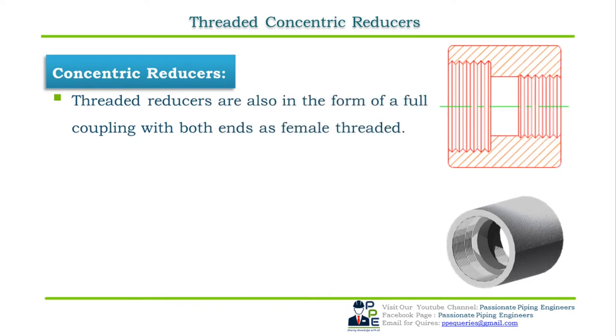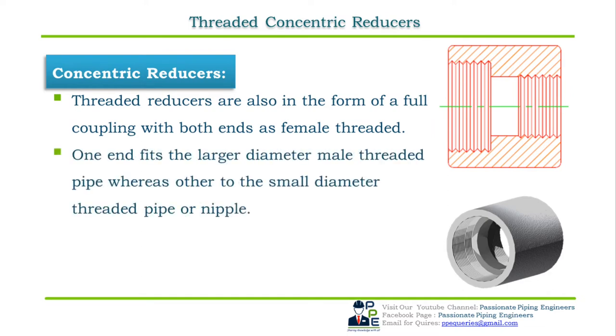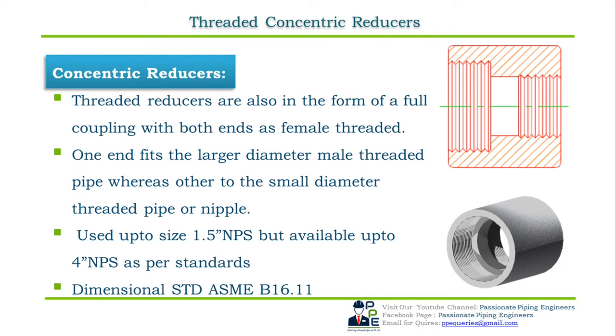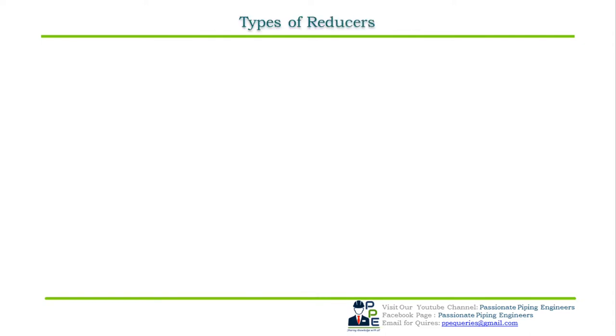Threaded concentric reducers are also in the form of a full coupling with both ends as female threads. One end fits the large diameter threaded pipe whereas the other fits the small diameter threaded pipe or nipple. Threaded concentric reducers are usually up to 1.5-inch NPS but also available up to 4-inch NPS. The dimensional standard for threaded concentric reducers is ASME B16.11.